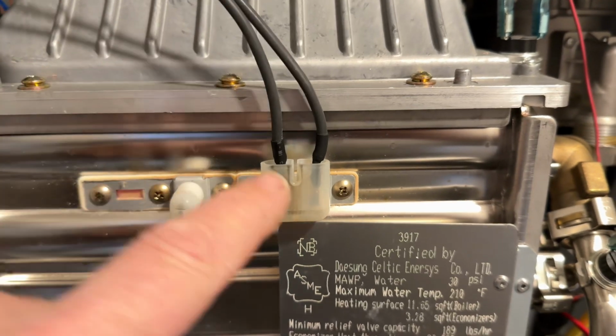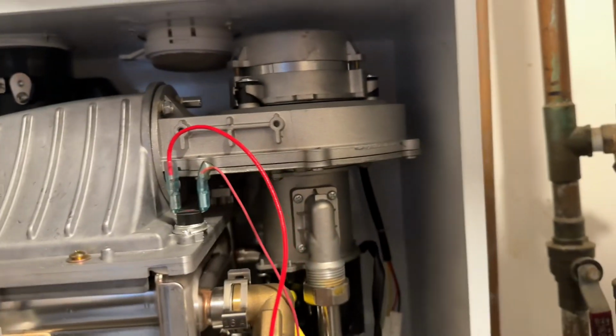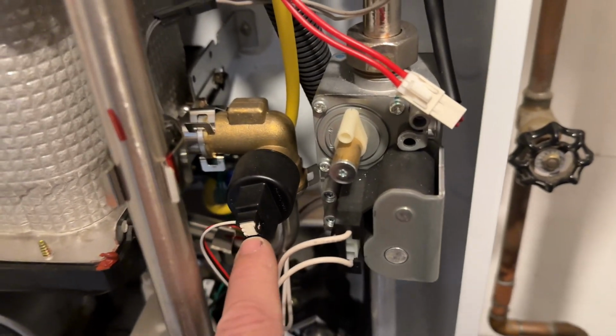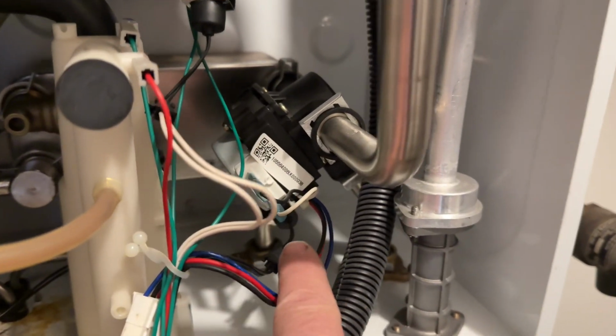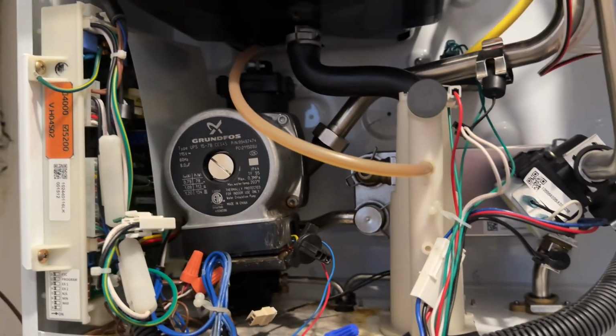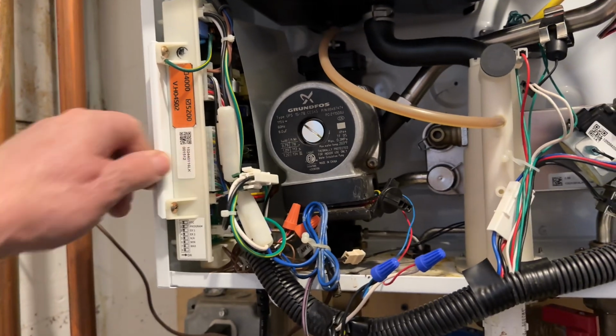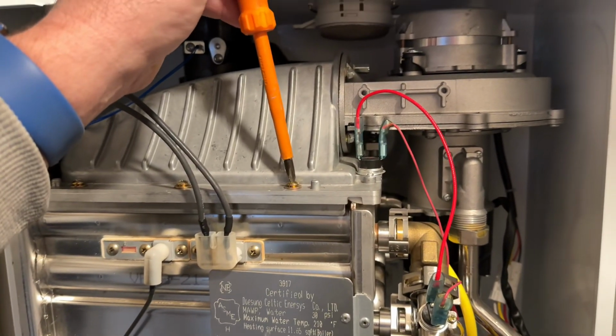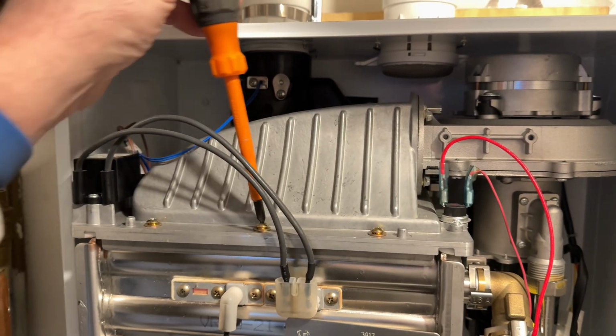Flame sensing cable, ignition cable going to the ignition module, ignition transformer, blower, venturi, gas valve, water pressure sensor. Motorized 3-way valve, internal circulator, condensate trap, control board. But there's our leak. Crack at the bottom of the heat exchanger. Bosch doesn't open until 9 a.m. Eastern time.